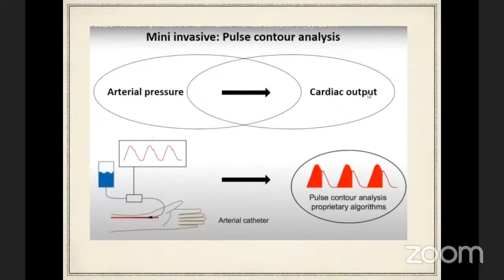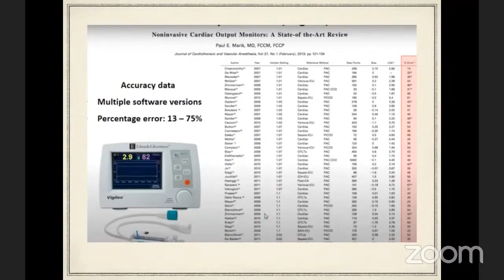This is a study of 2013 in the JCVA journal where they compared multiple software versions for accuracy, and they calculated a percentage error of 13% to 75%. We can see on the right side the percentage errors of 13%, 33%, 39%. So different percentage errors are there, and I would like to say that a percentage error of less than 30% is what is acceptable. Another study, published in Critical Care in 2016, showed that there was an improvement in the 4th generation FloTrac/Vigileo system for tracking the cardiac output changes.